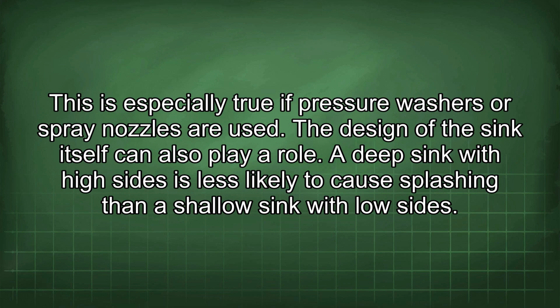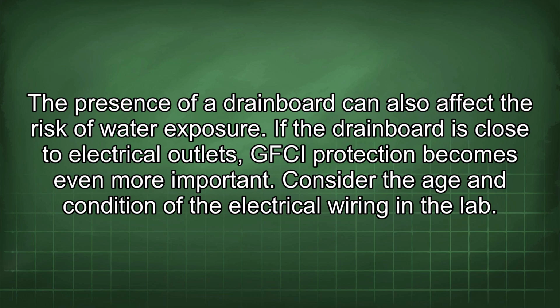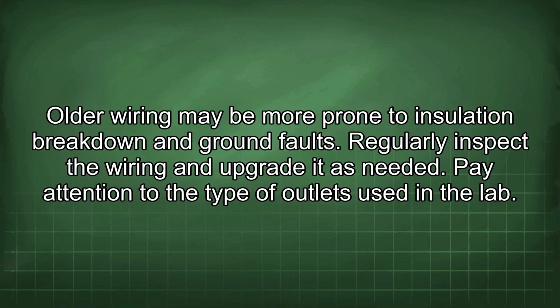The design of the sink itself can also play a role. A deep sink with high sides is less likely to cause splashing than a shallow sink with low sides. The presence of a drain board can also affect the risk of water exposure. If the drain board is close to electrical outlets, GFCI protection becomes even more important. Consider the age and condition of the electrical wiring in the lab. Older wiring may be more prone to insulation breakdown and ground faults. Regularly inspect the wiring and upgrade it as needed.